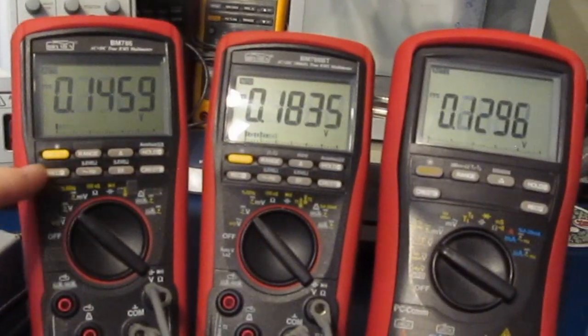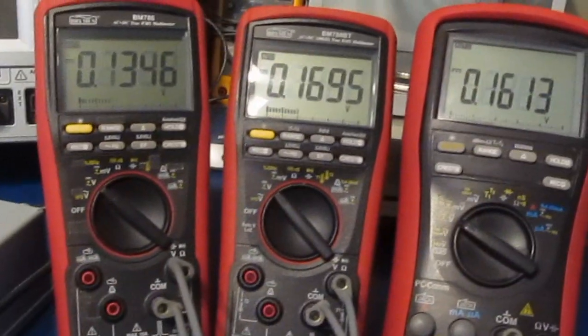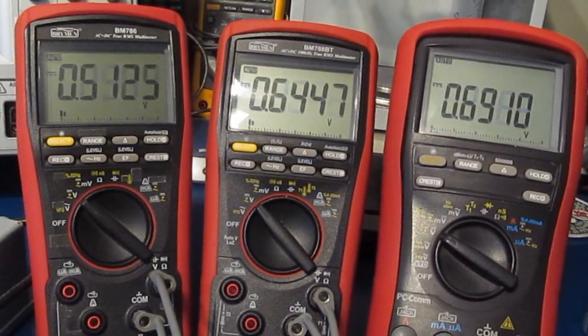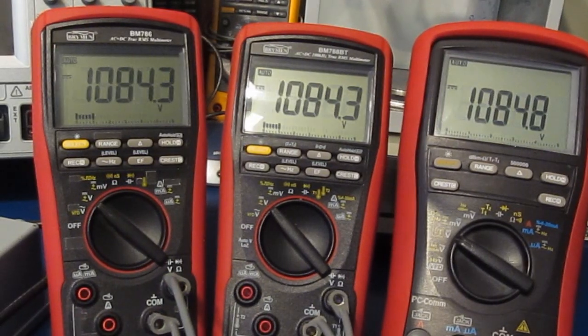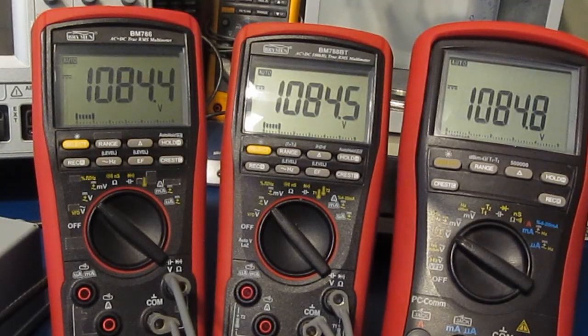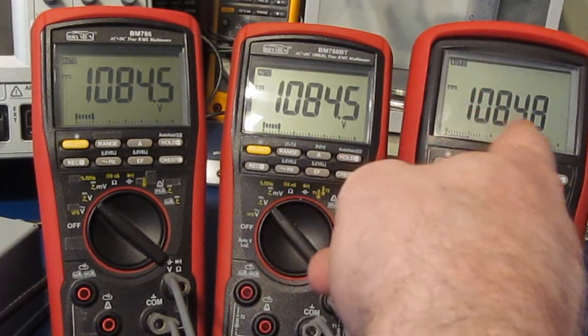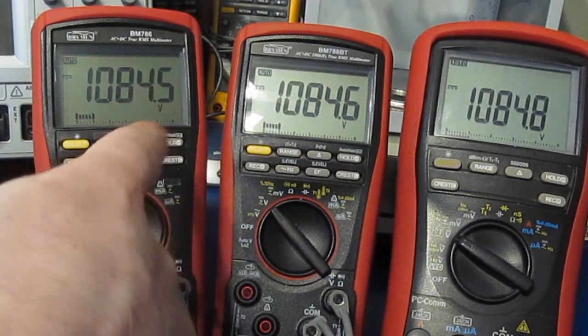So I did go back and realign the meter using the supplied kilovolts power supply and I used my HP 34401a as a reference. We'll go ahead and take them up to about a thousand volts, and you can see 1084.8, 1084.6, 1084.5.